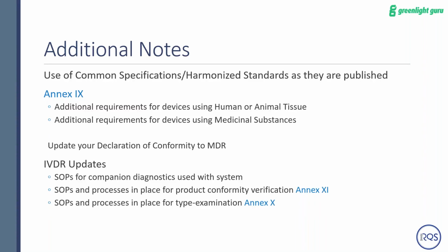Another thing we didn't touch much on that's important to say here is the new program for harmonized standards and common specifications. Everybody that has a CE mark device should be somewhat familiar with harmonized standards and the CE mark or EU rules around harmonized standards and making sure your device complies with those. As a new standard gets published, review that standard and make sure that you comply with it, or if new testing needs to be done on your device to the new standard, that you go ahead and get that testing done. So they're pretty proactive with that.